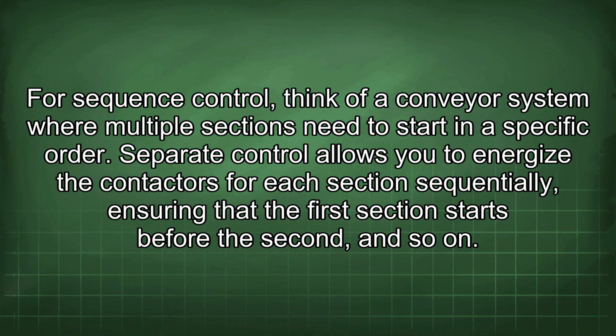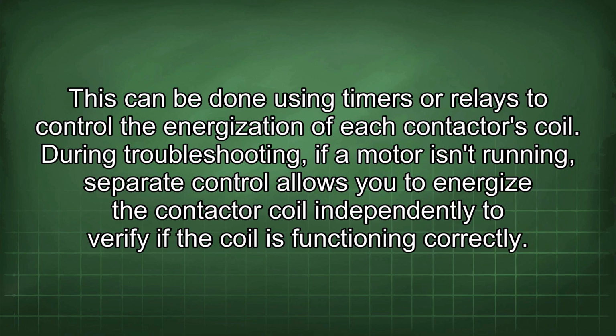For sequence control, think of a conveyor system where multiple sections need to start in a specific order. Separate control allows you to energize the contactors for each section sequentially, ensuring that the first section starts before the second, and so on. This can be done using timers or relays to control the energization of each contactor's coil.